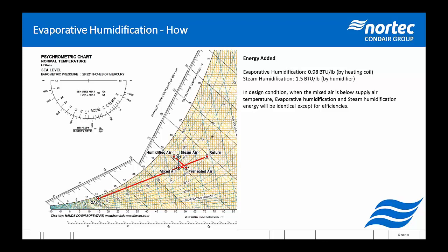So there is some math to be done by the building management system to make sure the mixed air temperature is heated enough to cool back down to set point. Admittedly, enthalpy wheels do complicate things, but on the other hand, we're able to design around them and design to continue to use as little energy as possible. Yeah, did I cover that question there?